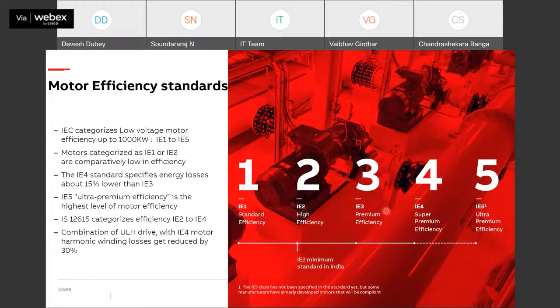Now, if you talk about the Indian market, the Indian cement industry is running with IE2 standards. Now things are moving, thanks to the cement industry, which is helping us supply IE3 premium efficiency motors. Things have started in the cement industry for demand of IE3. Also, IE4 will be the minimum standard in Europe in 2023. I hope soon it will come in India also. When we talk about the impact on decarbonization, a combination of low harmonic drives with IE4 motors can reduce winding losses by up to 30%, which will definitely improve the overall performance of the motor, of your process plants, and directly impact the productivity of the plant.